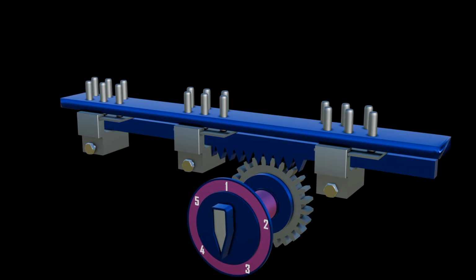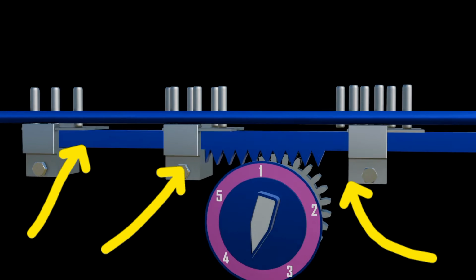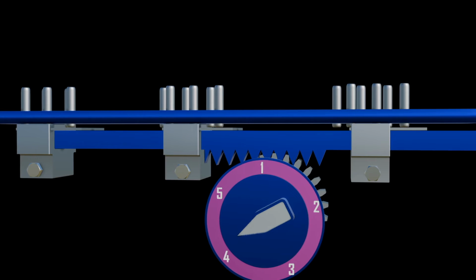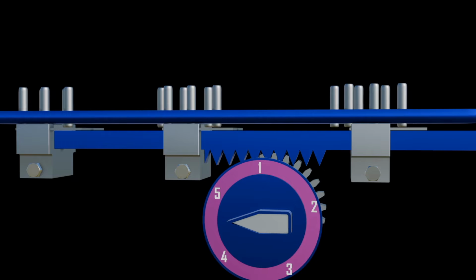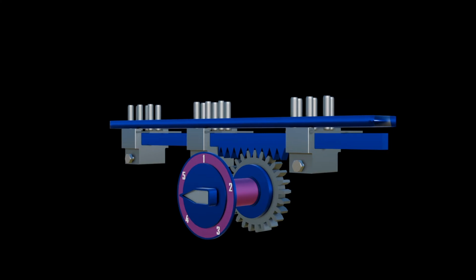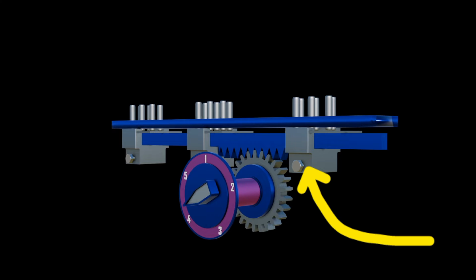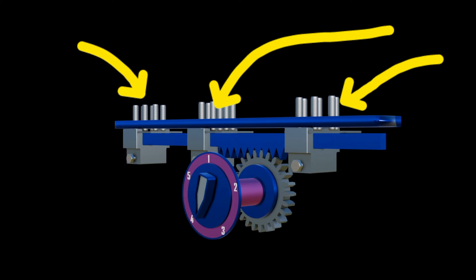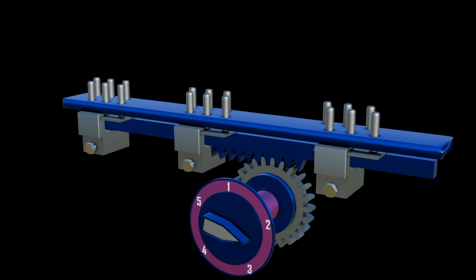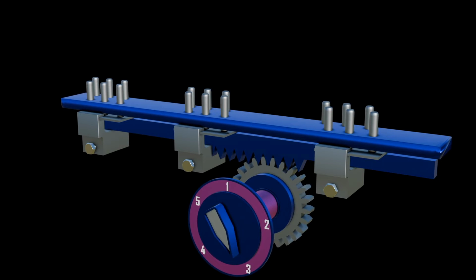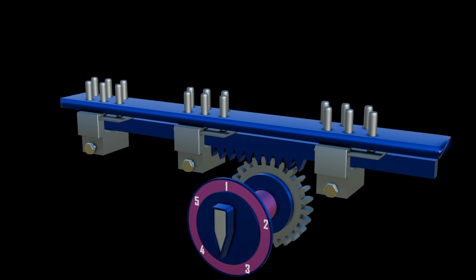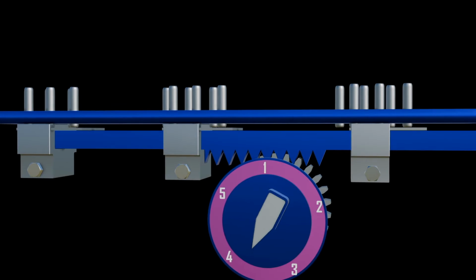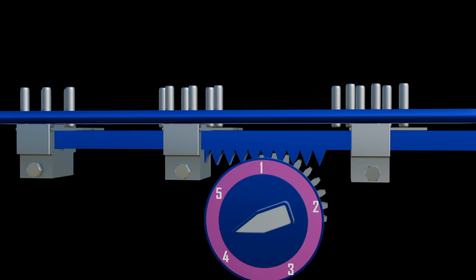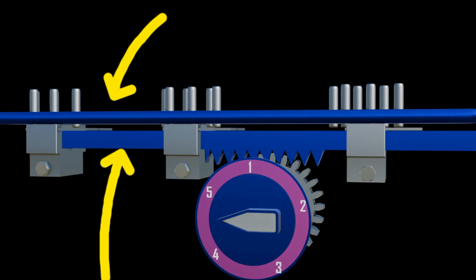The linear gear is connected to the tap selector switch mechanism. As the linear gear moves along its track due to the rotation of the round gear, it pushes or pulls the tap selector switch, causing it to move to the desired tap position. Also, tap leads are connections that lead from the tap selector switch to the transformer winding. The selected tap position determines which winding turns are active, thus altering the transformer's turns ratio. Tap insulation is provided to ensure that the tap leads are electrically isolated from each other and from the transformer core.